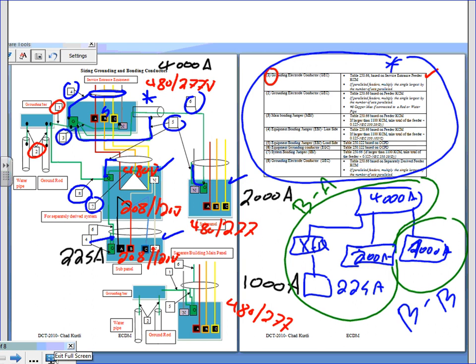Number 7, I want to remind you guys by where number 7 is. Move, Chad. Oops, there you go. You guys see where number 7 is? Number 7 is actually the system bonding jumper. Right? Is that what we call it? System bonding jumper. For the separately derived system. Now, Spencer, I created a delta Y. I created my new neutral. That's called separately derived system. Every time you create your own neutral through a transformer, most of the time, or generator, or UPS, then that's called separately derived system. You bond the neutral to the ground. Can you guys see where number 7 is? Number 7 is right here, bonding the neutral to the ground.